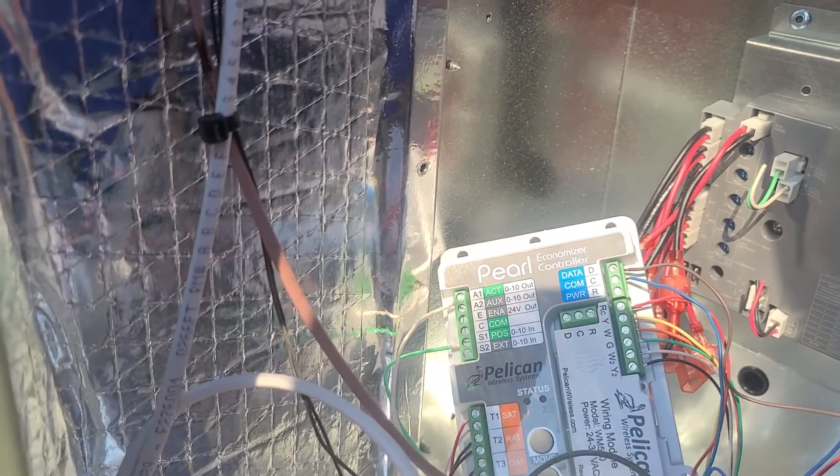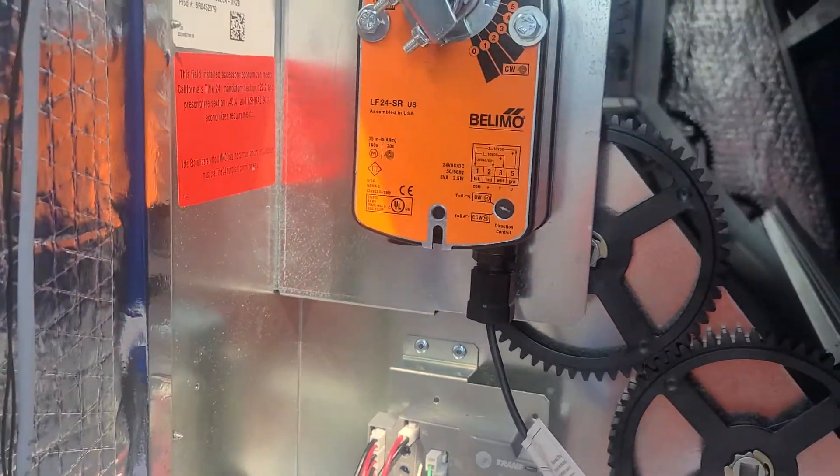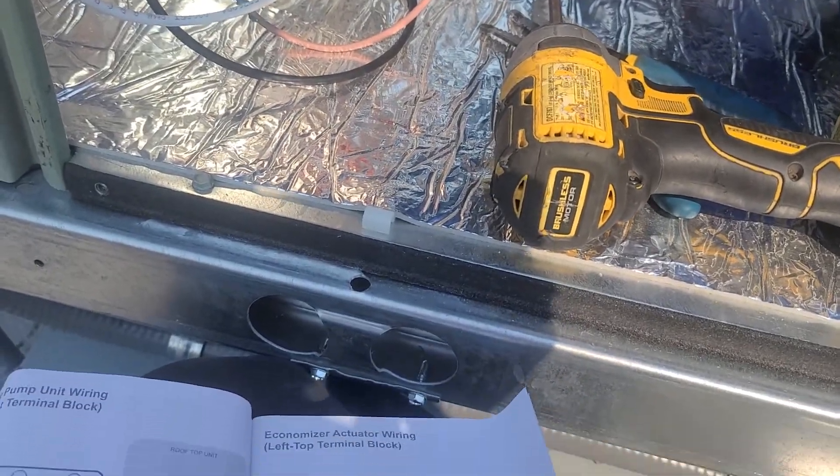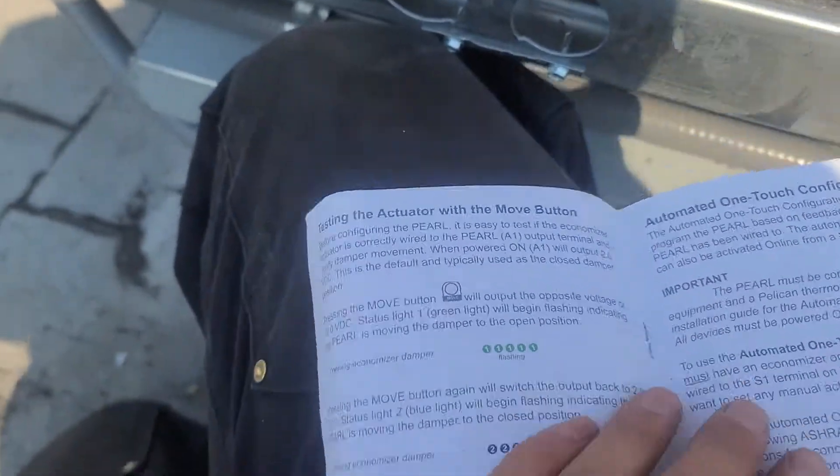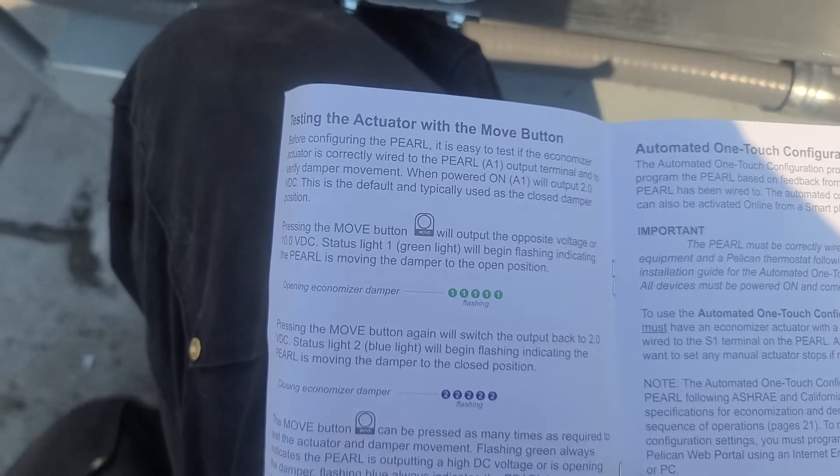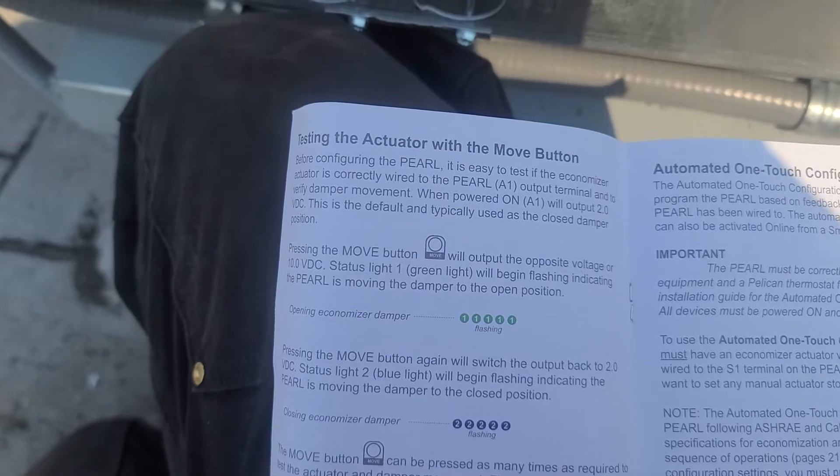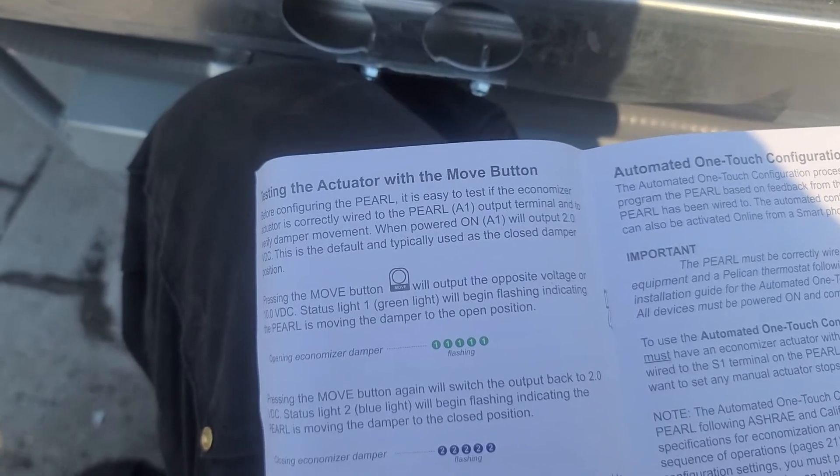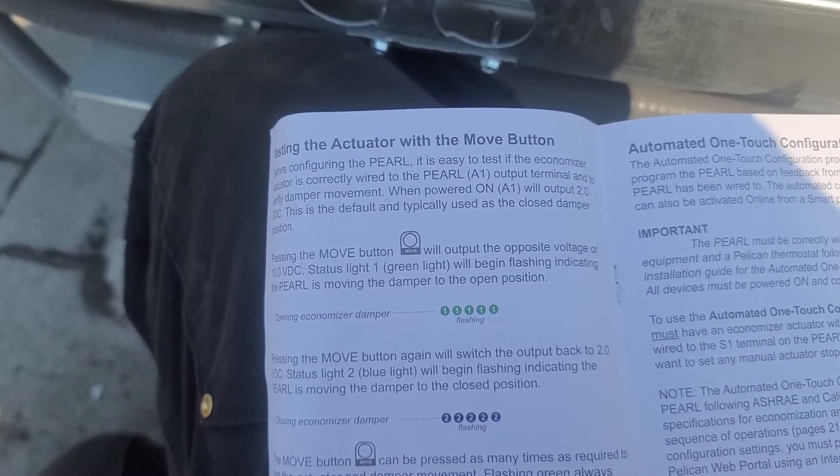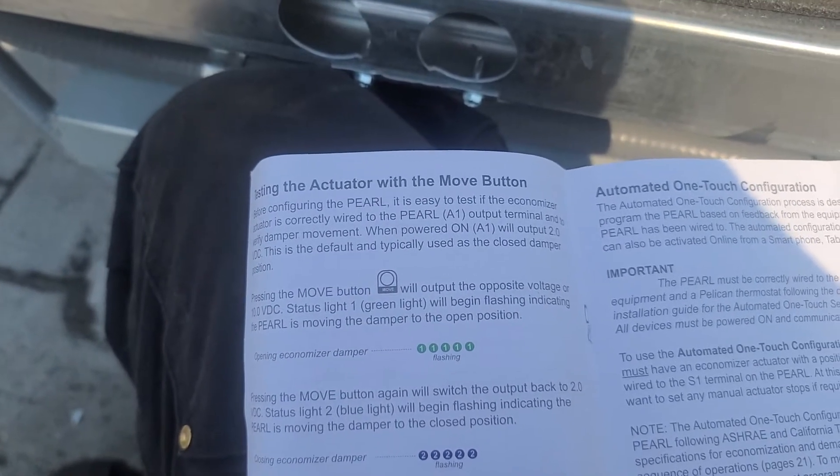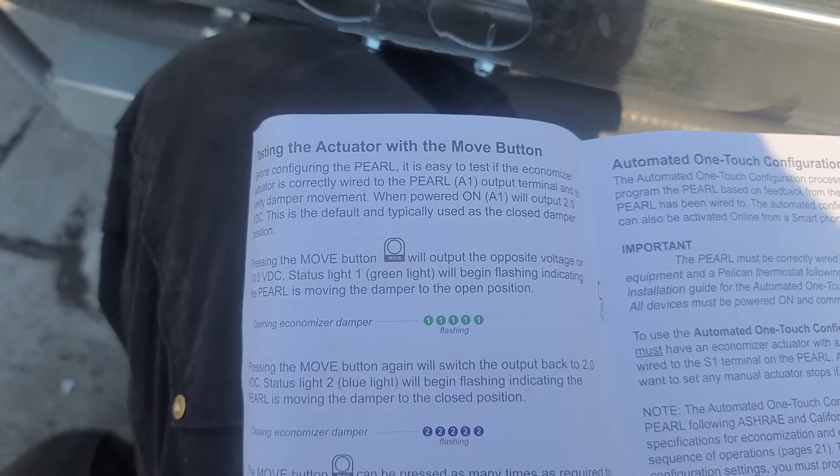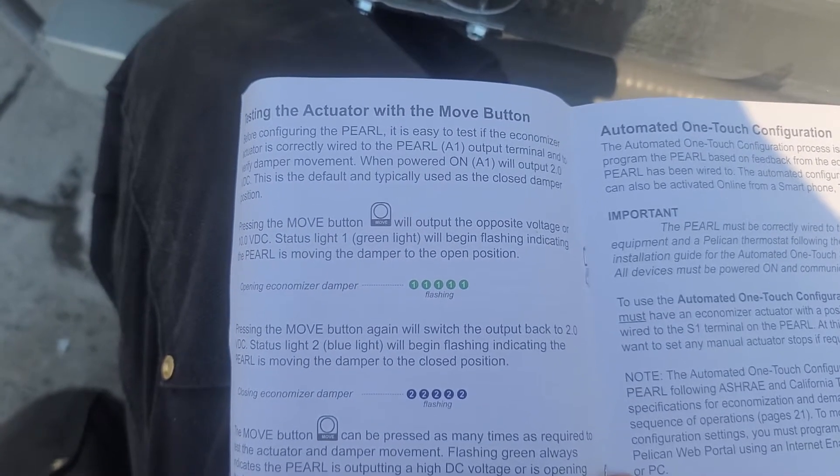As far as testing this thing, there's like a self test you can do. Testing your actuator is right here and it kind of goes through step by step on how to go through everything to make sure it's opening and closing properly. And if it's actually backwards, which happens I don't know 50% of the time, there's literally just a button you can hit and it tells you when to hit it and it will reverse it so it's opening when it's supposed to and closing when it's supposed to. You can kind of set this up when you're setting it up. You basically just go to the Pelican website and after you do your full setup of everything, you're doing pretty much all the setups on your phone.